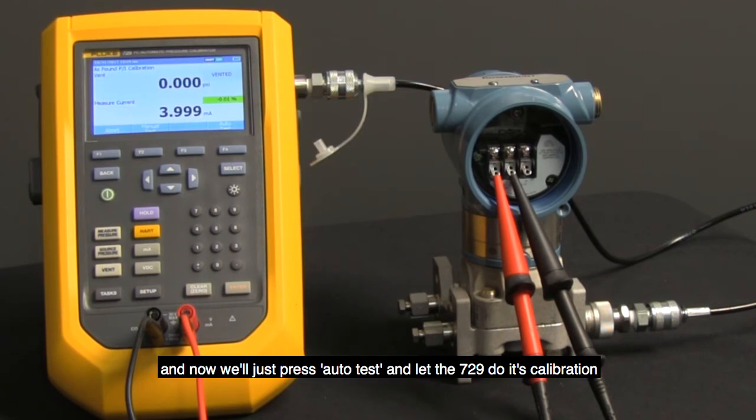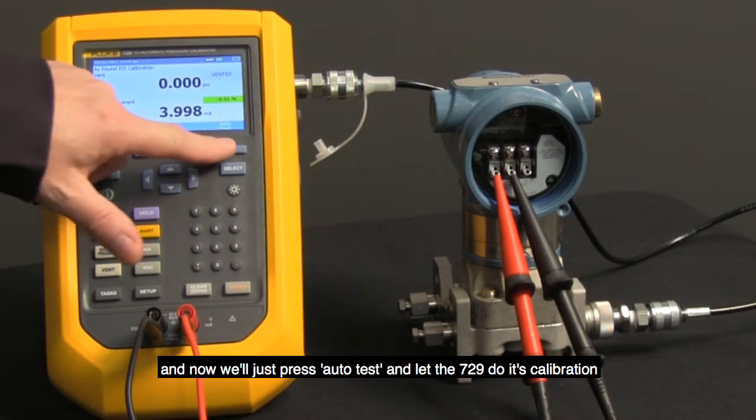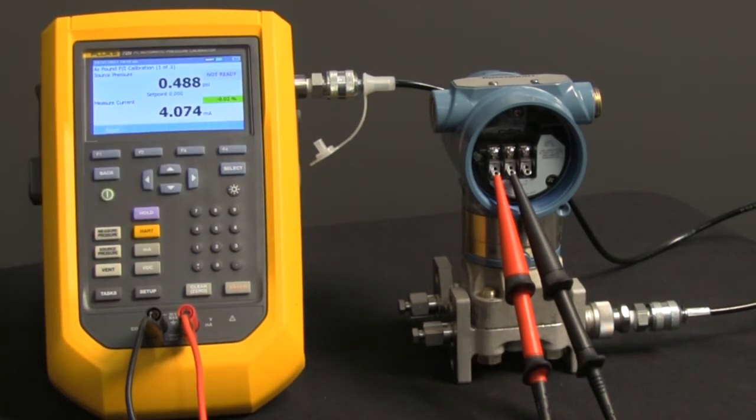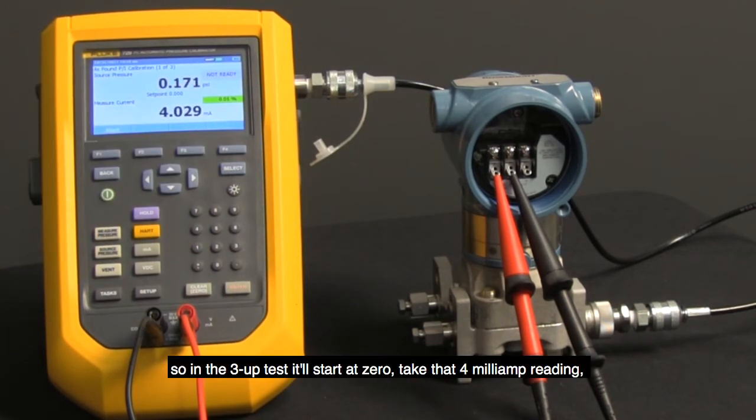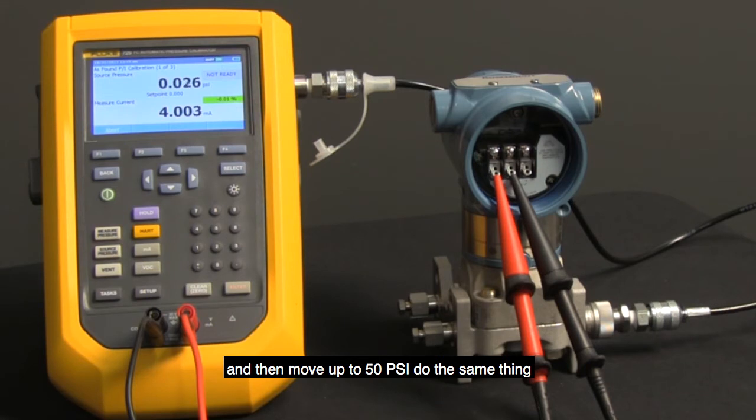And now we'll just press auto test and let the 729 do its calibration. So in the three up test, it'll start at zero, take that four milliamp reading, and then move up to 50 PSI and do the same thing.